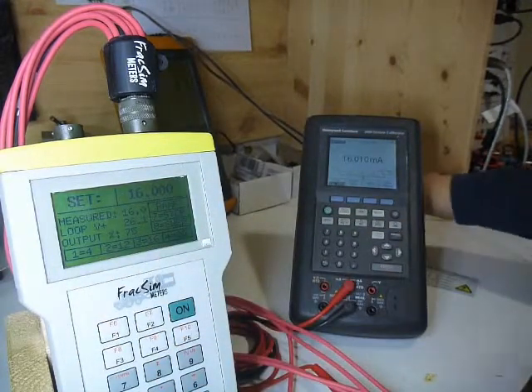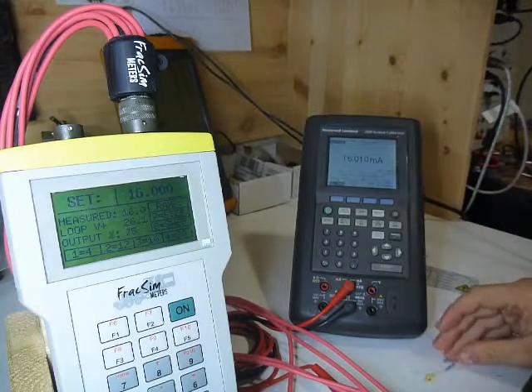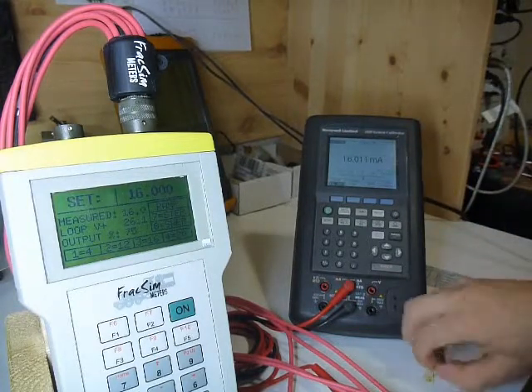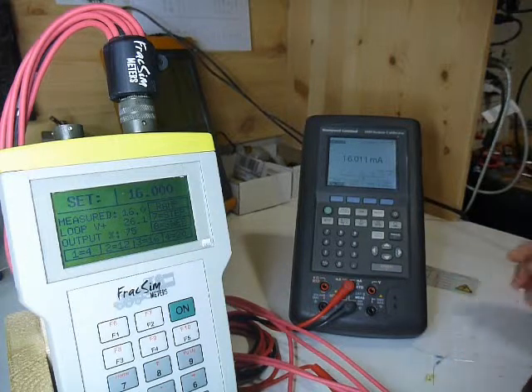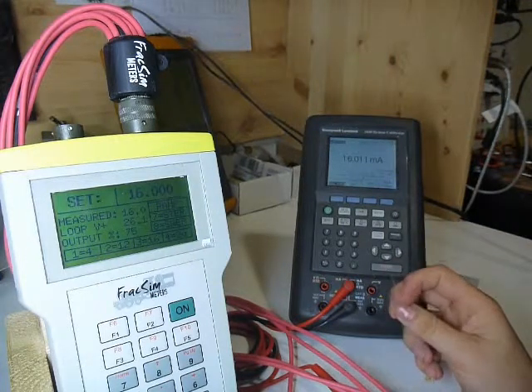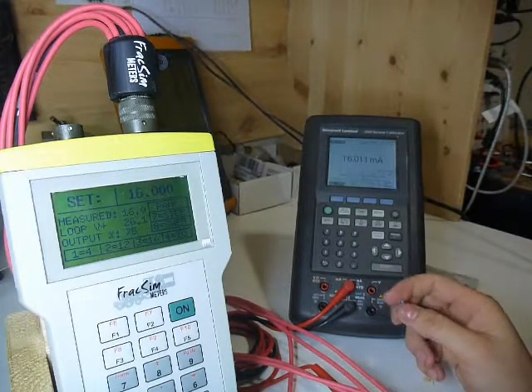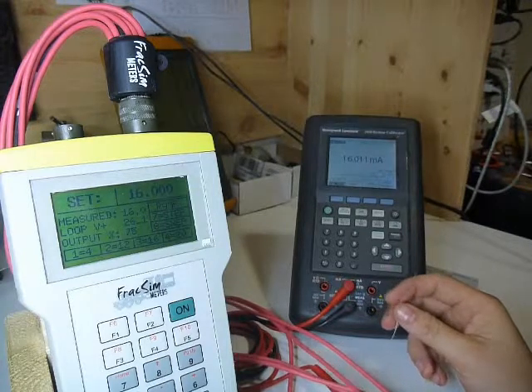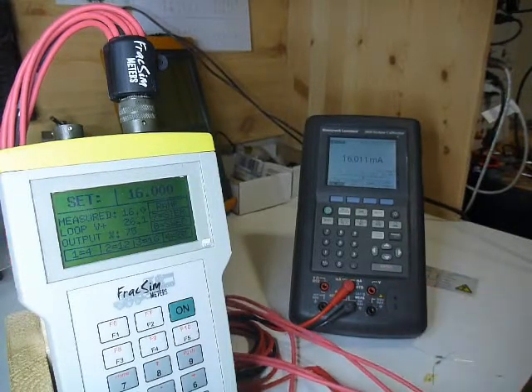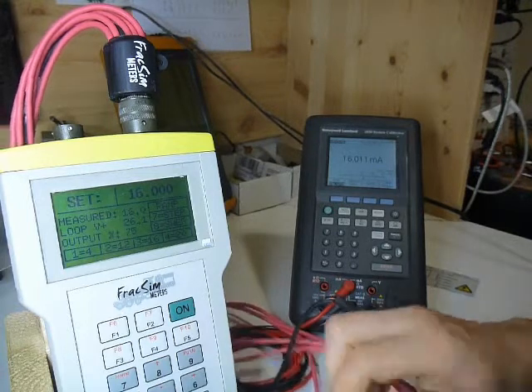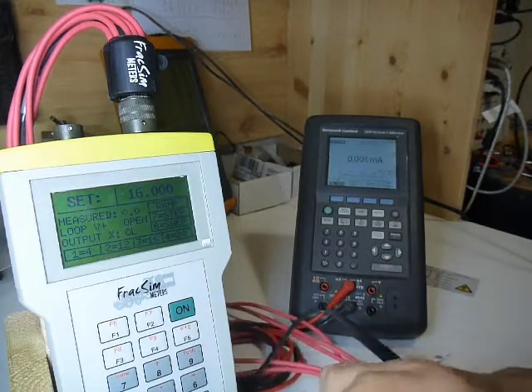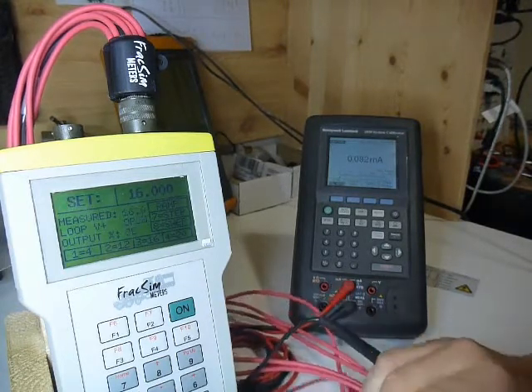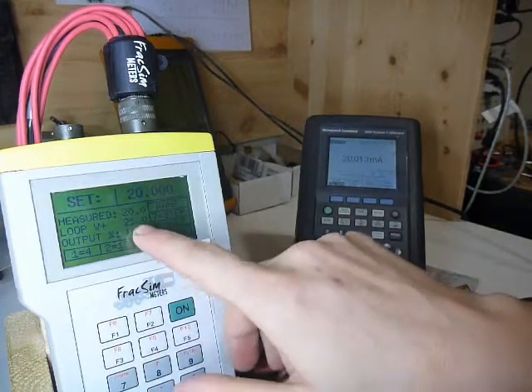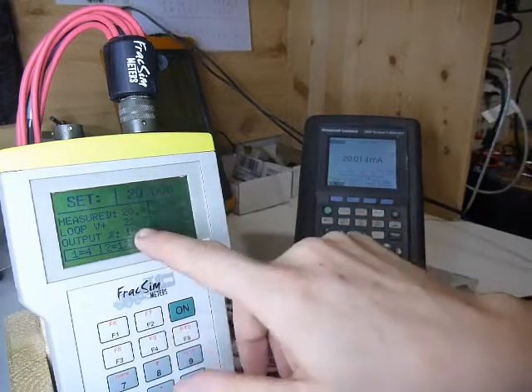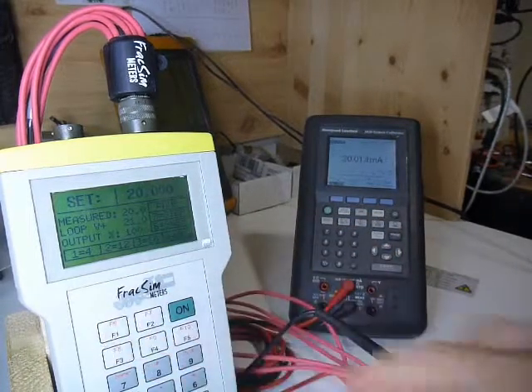But what I want to do to demonstrate more with the loop voltage is put a resistor in series. I happen to have a 250 ohm resistor here, and I'm going to put that at the output of the Fracsim to demonstrate a load. So out of the FracSim, when it goes into the Fluke here, I'm just going to put this resistor in here. And so what we're going to do is go to 20 milliamps, and you'll see we have about 20 milliamps, we're about 21 volts.